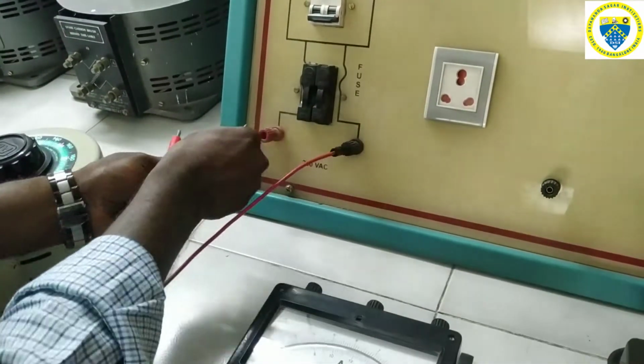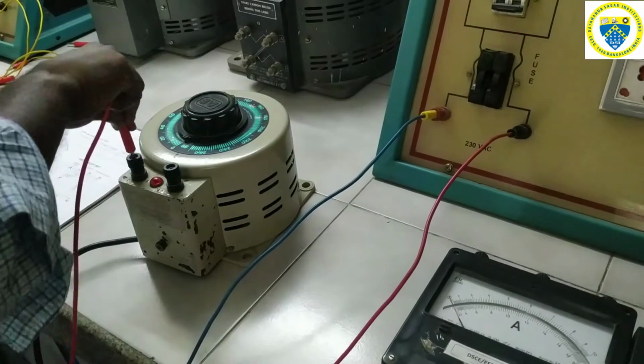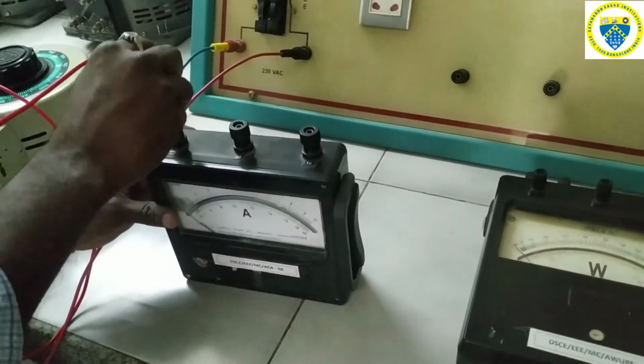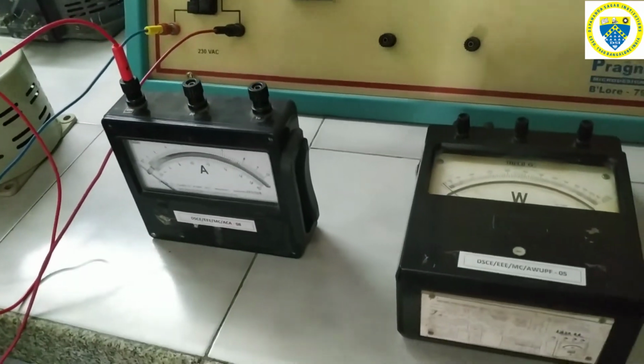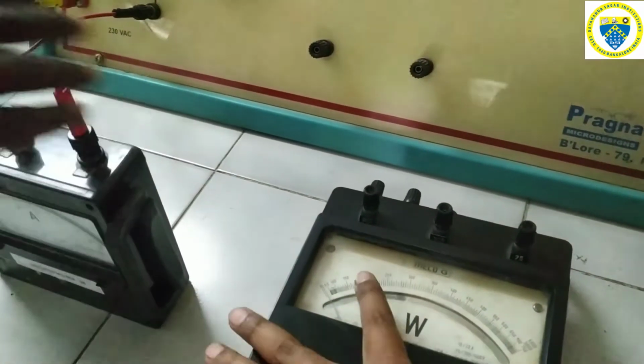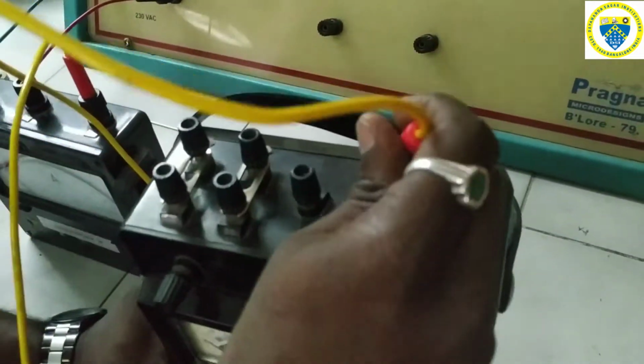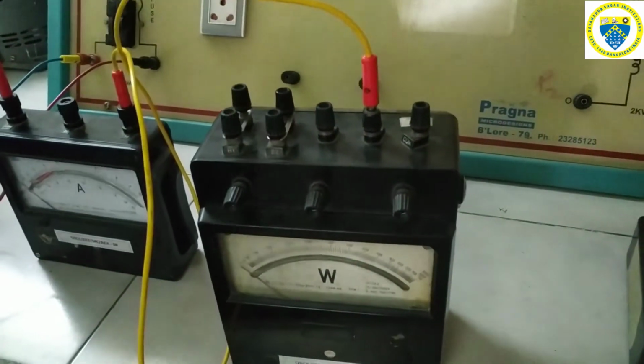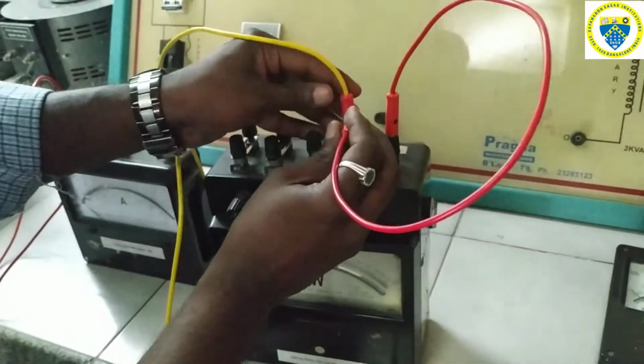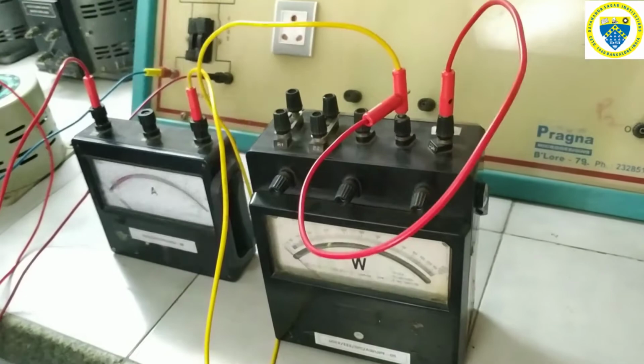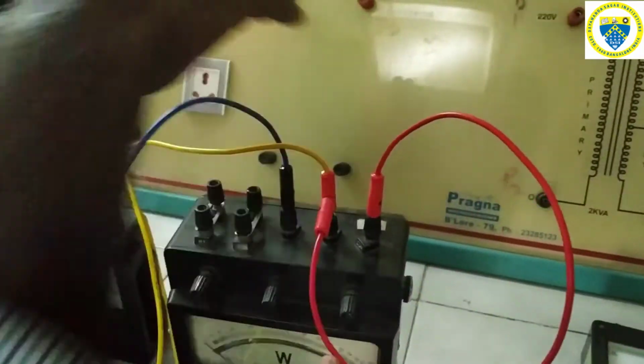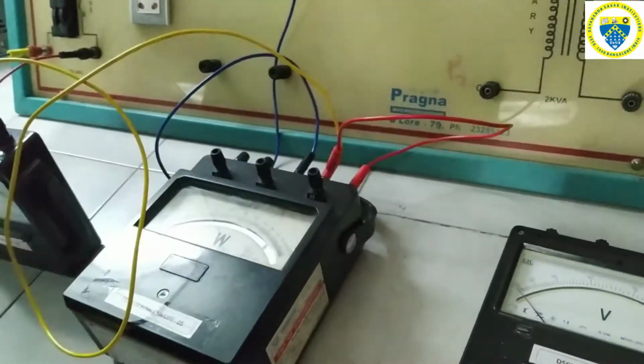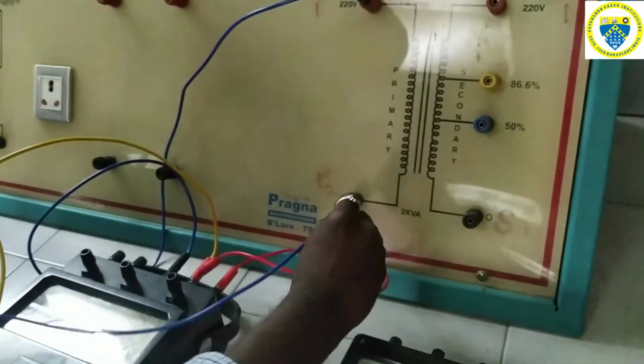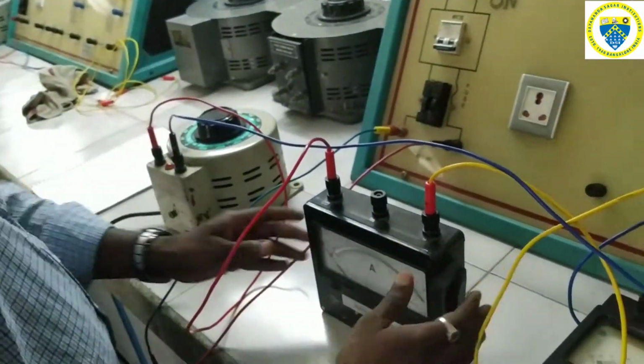Now from the mains the auto transformer is excited first, then the connection from the auto transformer is given to the ammeter, again the same series connection first, and then from the ammeter to the wattmeter. The M terminal is connected first, then M and C of the wattmeter are shorted, then the L line terminal of the wattmeter is given to P1, and P2 should go back to the neutral terminal of the auto transformer.